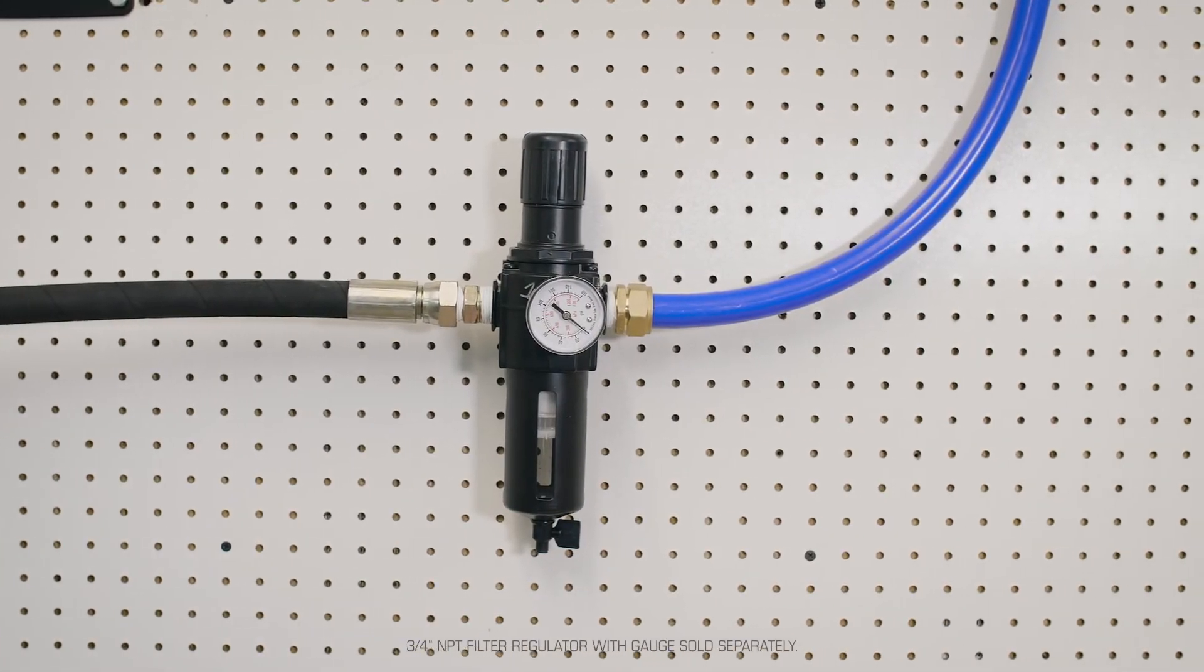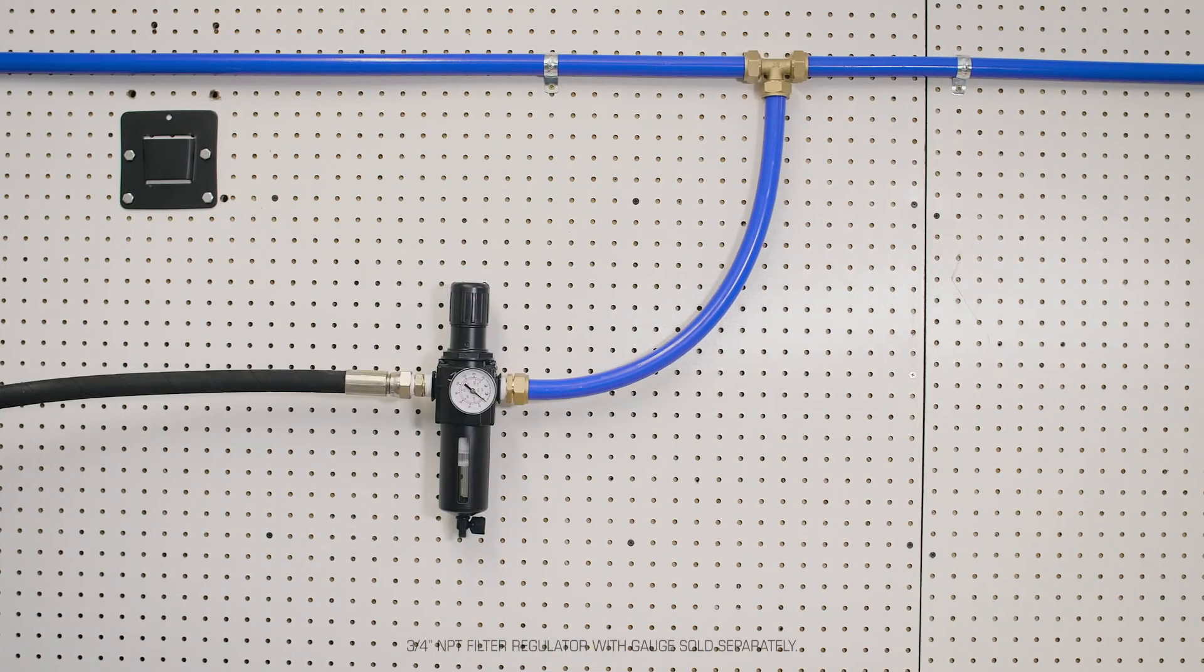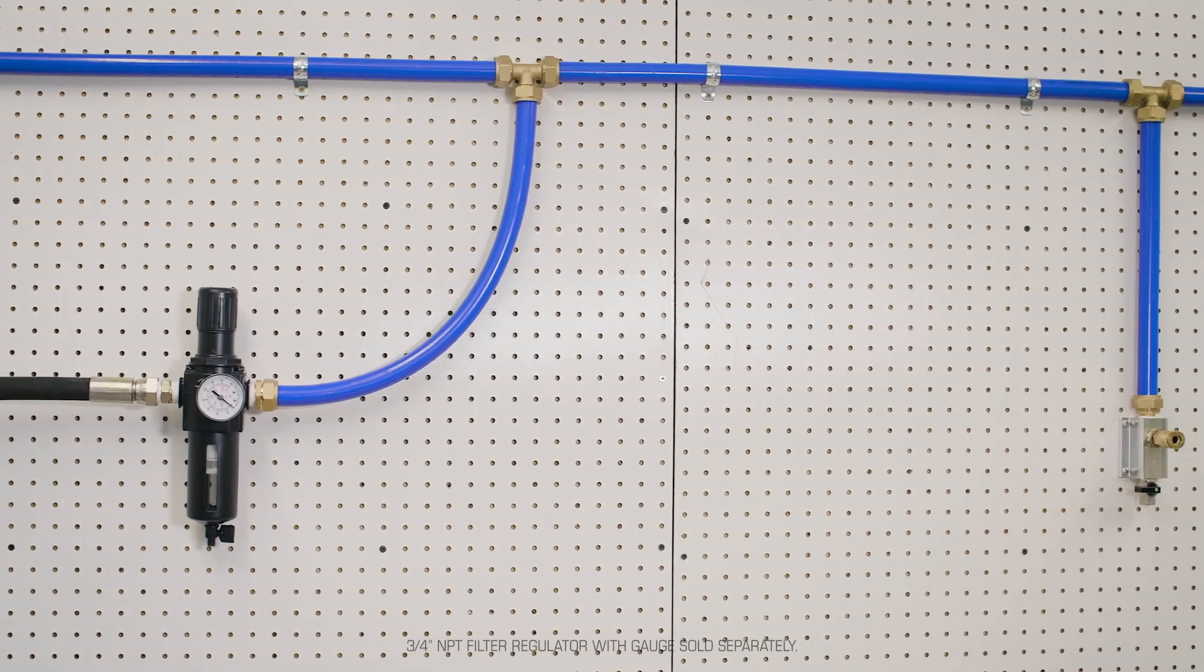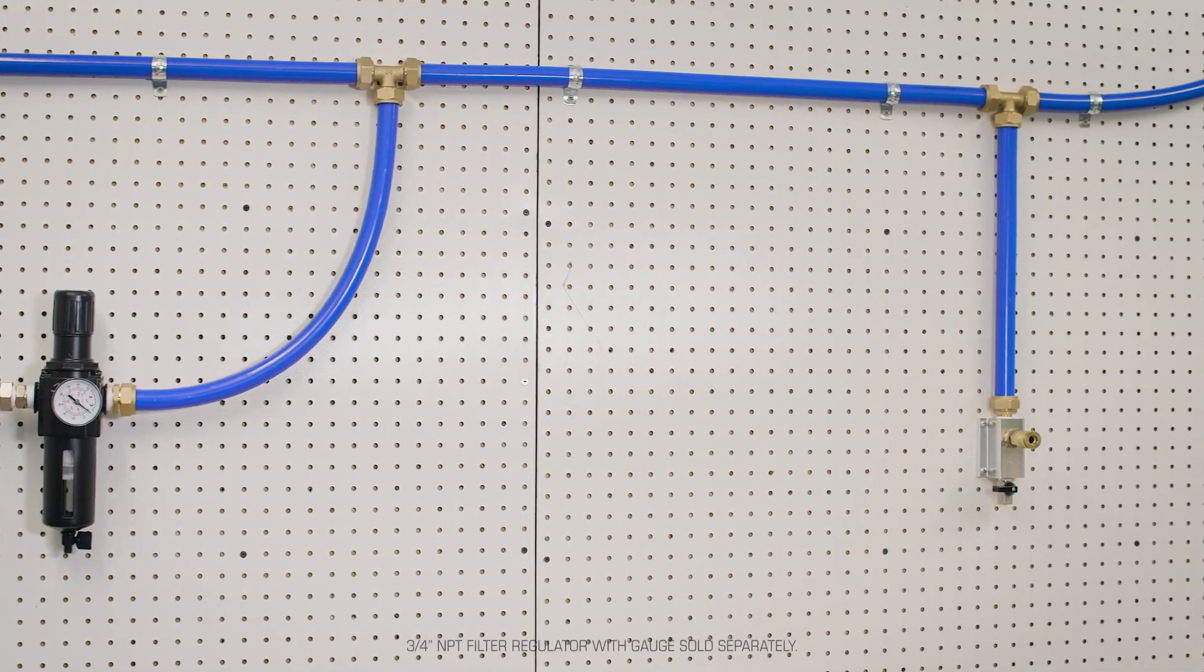It is recommended to have a three-quarter inch hydraulic hose and a three-quarter inch filter regulator installed between your compressor and the air piping system to maximize air quality and output.